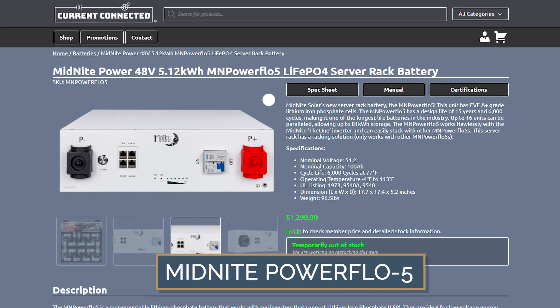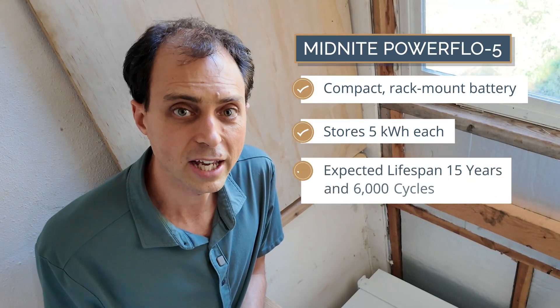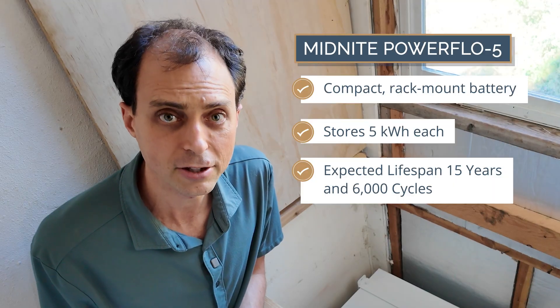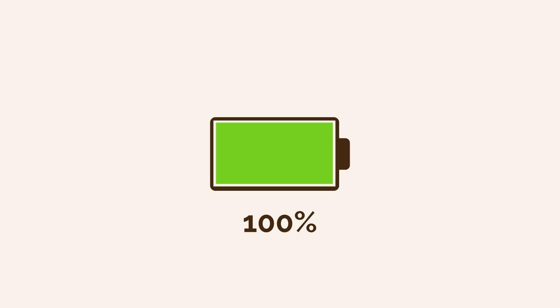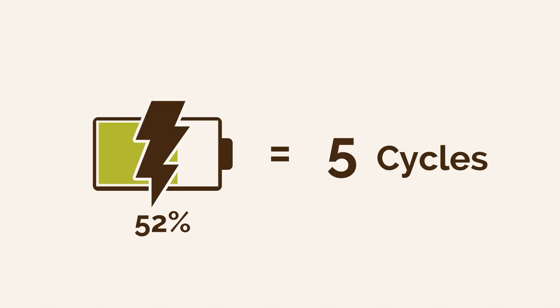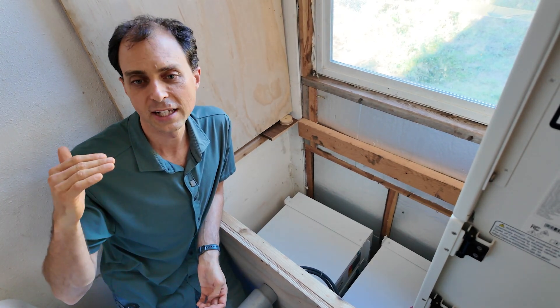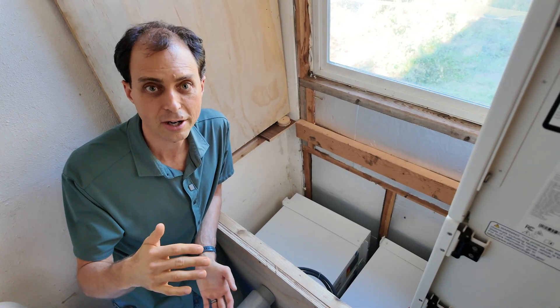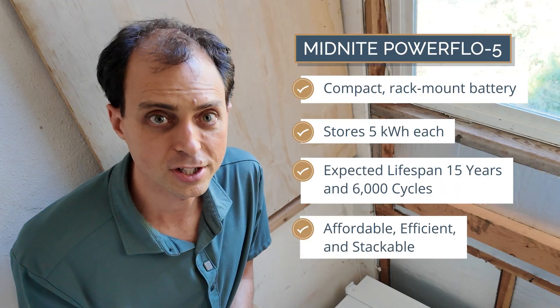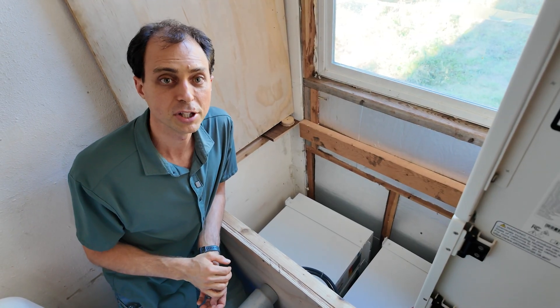They come in two main versions. The PowerFlo-5 is a compact rack-mounted battery storing about 5 kilowatt-hours each, with an expected lifespan of at least 15 years and 6,000 cycles. A cycle is when you start fully charged, discharge down to around 20%, and charge back up — that's one cycle. After 6,000 cycles, these batteries will still hold 80% of their rated capacity. They're affordable, efficient, and you can stack them six high — up to 16 total in one complete battery bank.